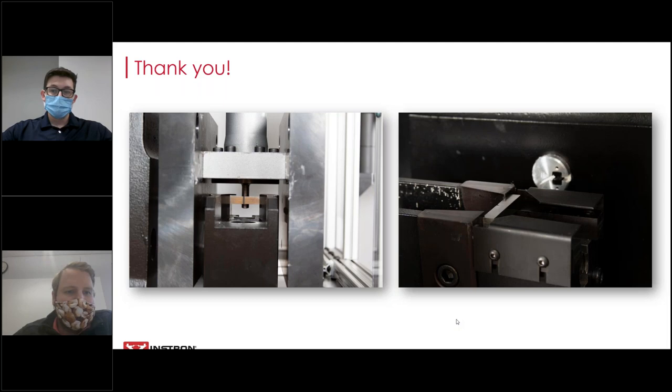During the resolution piece, you were explaining the dials, and there was a question there about where the factor of 25 comes from. I think that's in regards to 25 times the resolution of your testing machine. Yeah, so the 25 times comes straight from the standard, ASTM E23. The full standard says 25 times the resolution at 15 joules. The reasoning for the 15 joules, if you remember older weight scales, you know, 0 to 100, is scaled evenly, but everything after, you might go up to 600 and the scale is way off. So that's kind of where the 15 joules comes from. But the 25 is just what's dictated in the standard. Thank you. I think that makes perfect sense.